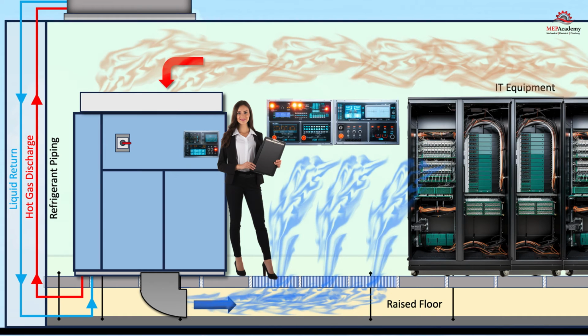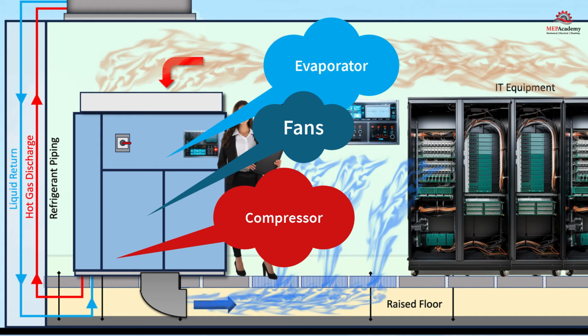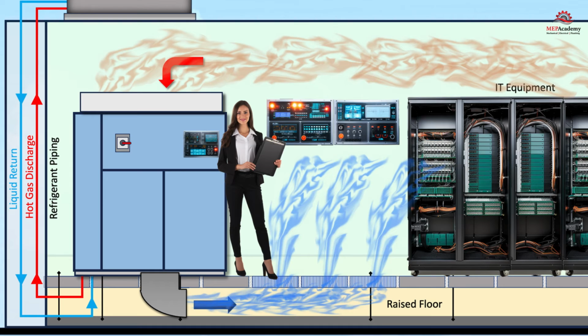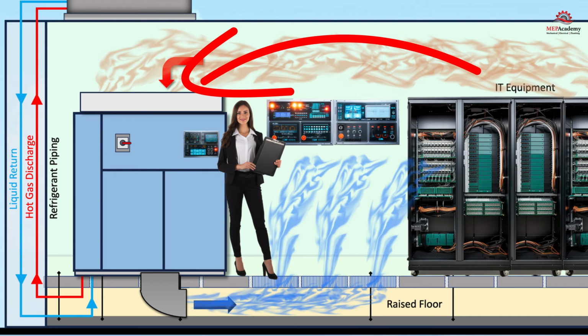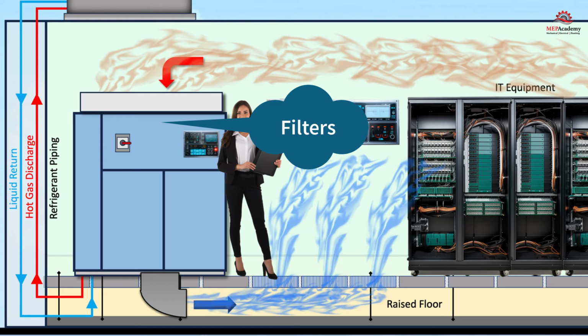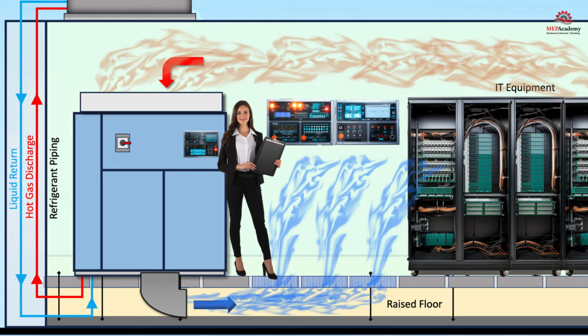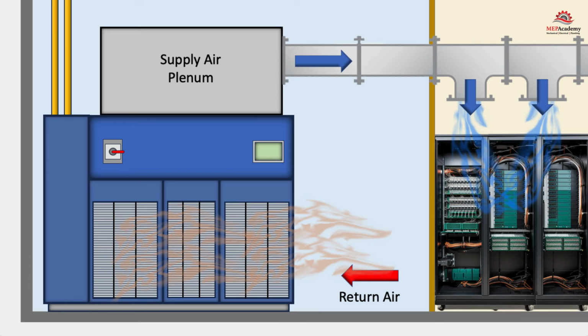The indoor unit will house the compressors and evaporator coil. The liquid refrigerant will go through the electronic expansion valve before entering the evaporator coil. Warm air from the IT equipment racks will enter the top of the unit before passing over filters, then through the evaporator coil where the heat gets absorbed. The now cooler air will be sent out the bottom of the unit to the underfloor supply plenum where it will travel through perforated floor tiles and re-enter the IT equipment to repeat the cycle. There are other styles of the indoor unit where there is no need for a raised floor and where the return air is located on the bottom front of the unit. The supply air will come off the top.